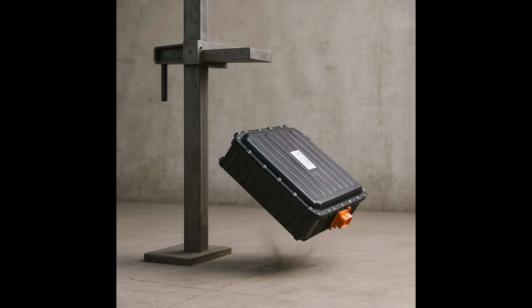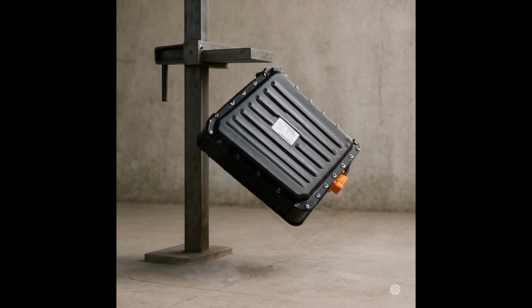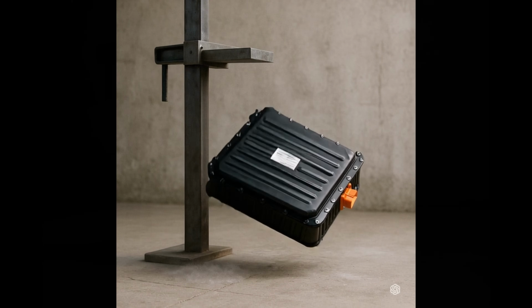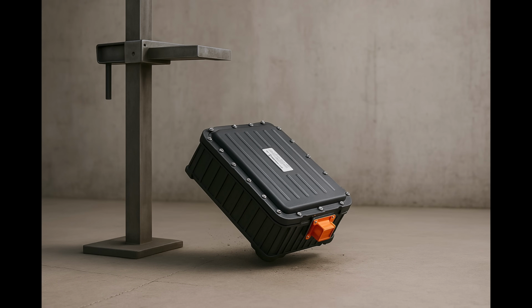Drop testing simulates real-world handling abuse scenarios, such as drops during manufacturing, assembly, transportation, and maintenance. These are uncontrolled events. Battery modules or full packs may be dropped during shipping by a technician or even during installation. You'd be surprised how often batteries are damaged before they even get powered up. The test parameters for drop testing often include a test at a height of 1 meters to 2 meters depending on the application and standard followed.